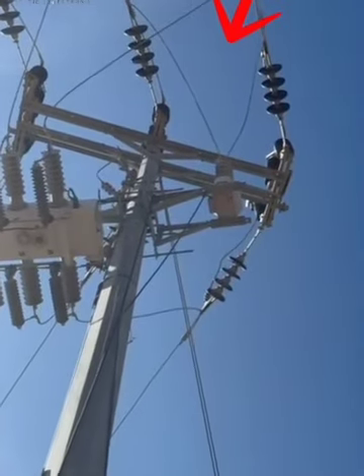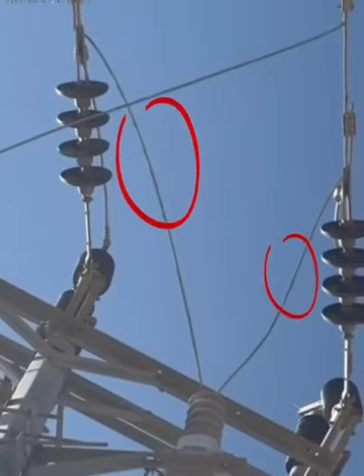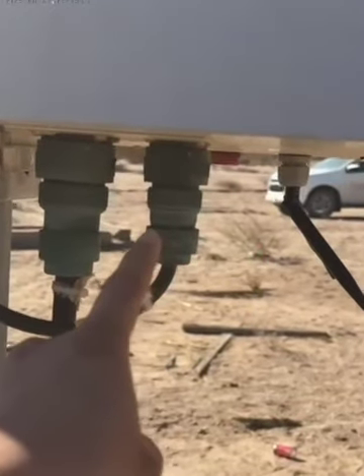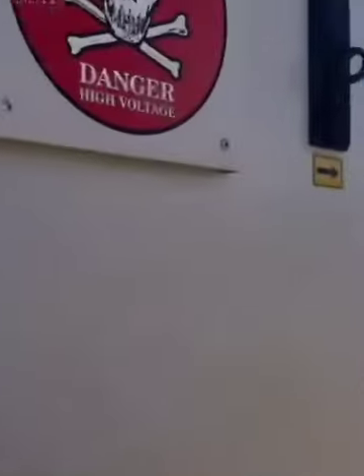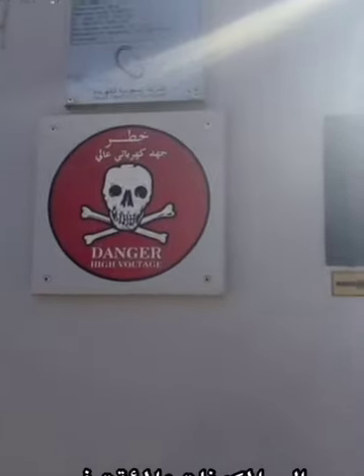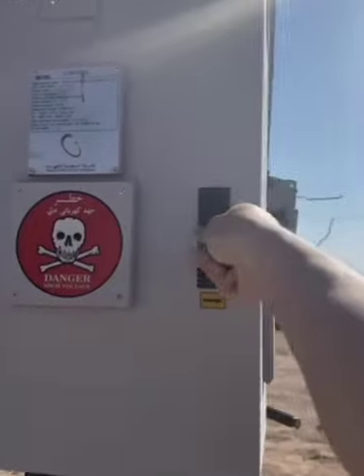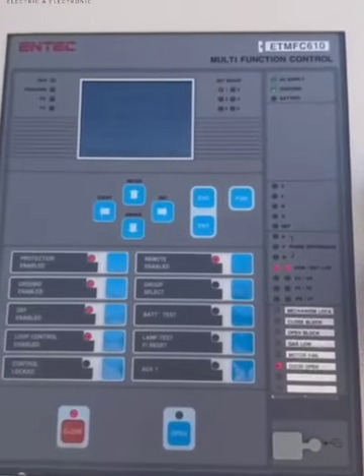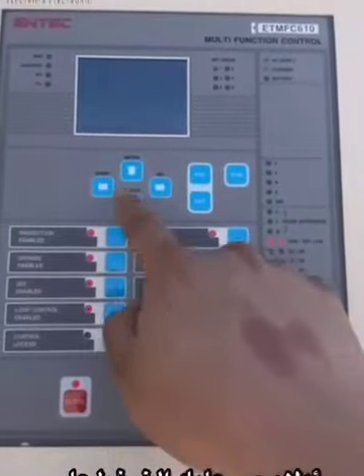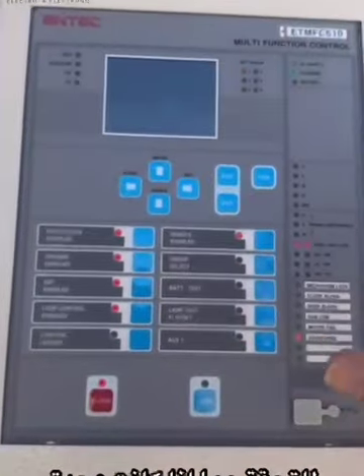If you can see here, the VT, the primary is on the line, and the secondary line is coming down straight to the controller right here. So this is the power cable that comes from the PT into the controller, giving power to the components and relay inside the controller. Right now the controller is turned on. If the LED is off and you don't see any light, first you should press the awake button to check if the controller is on.